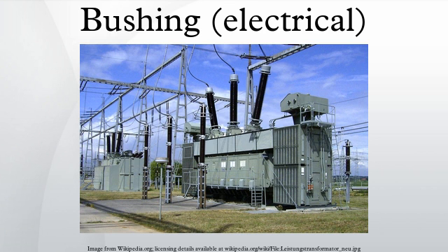In the case of resin, the paper is film-coated with a phenolic resin to become synthetic resin-bonded paper, or impregnated after dry winding with epoxy resins, to become resin-impregnated paper or epoxy resin-impregnated paper. SRBP insulated bushings are typically used up to voltages around 72.5 kV. However, above 12 kV, there is a need to control the external electrical field and to even out the internal energy storage, which marginalizes the dielectric strength of paper insulation.